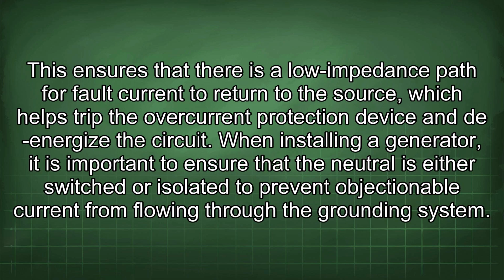This ensures that there is a low impedance path for fault current to return to the source, which helps trip the overcurrent protection device and de-energize the circuit. When installing a generator, it is important to ensure that the neutral is either switched or isolated to prevent objectionable current from flowing through the grounding system.